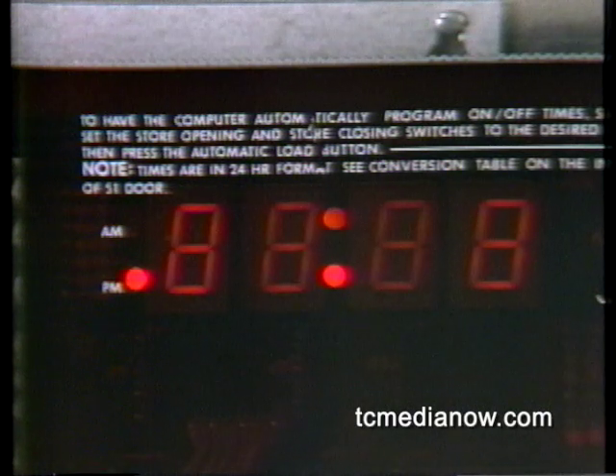If a power failure lasts longer than 35 minutes, however, battery power runs out. The clock face will look like this. When power is restored, the system clock will require reprogramming. Follow the instructions on page 2 of the instruction booklet stored inside the panel. In the event the system fails to change modes at the desired time, for example, power to the cooking equipment does not come on when programmed, the most likely cause of the error is that a PM time cue has been recorded when an AM was intended, or vice versa. Carefully check the appropriate time cues using the display time buttons and correct the cues as required.